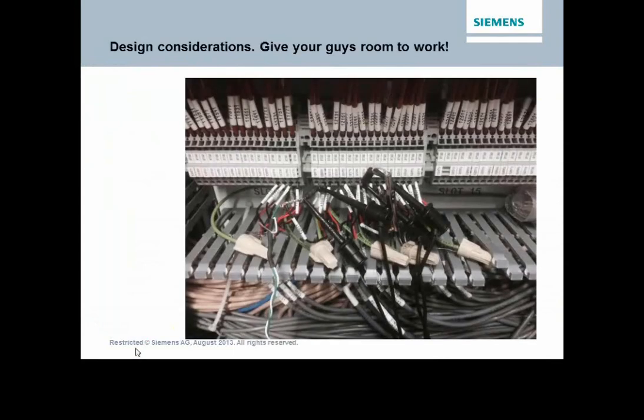When it comes to design considerations, one of the things is real estate in the marshalling panels is quite often at a premium. But what you save in material costs or initial costs can be lost down the road in terms of trouble with setting up and communicating with devices. Here we have some 24, 26 devices in about a 6-inch area. This is double stacked wiring in a marshalling panel, and spring loaded as opposed to screw connections. So taking about 5 minutes to get a wire out, 5 to 8 minutes to make a connection to be able to talk to a single device. So kind of a bit of a pain in terms of trying to set up and do commissioning.